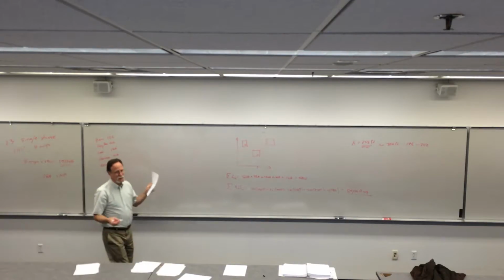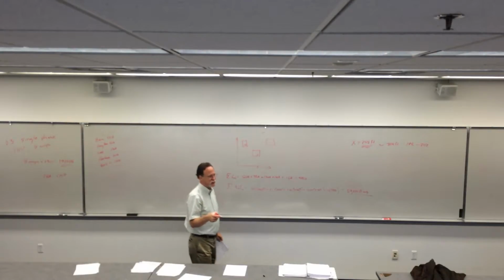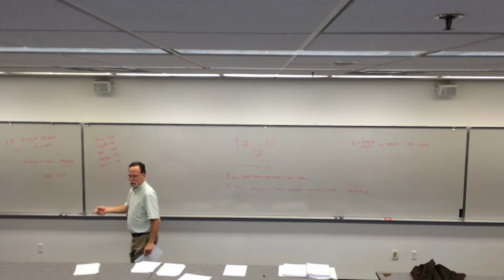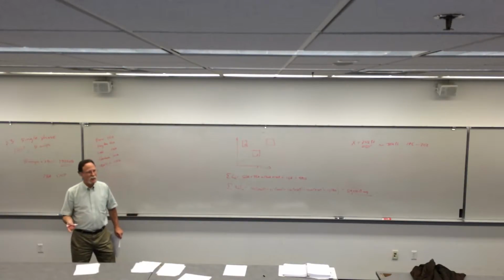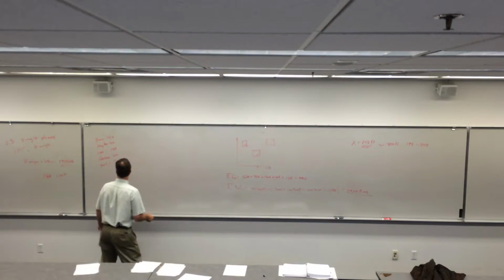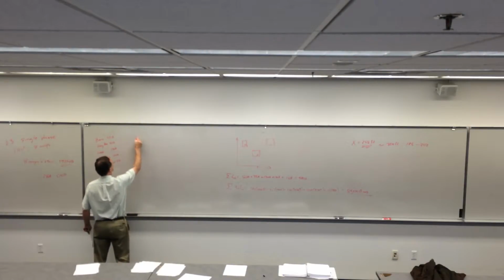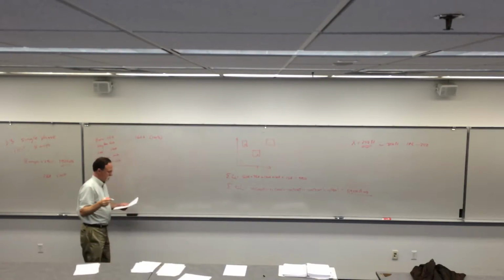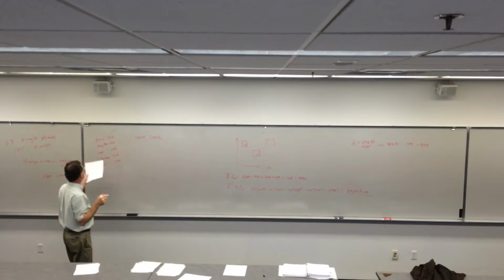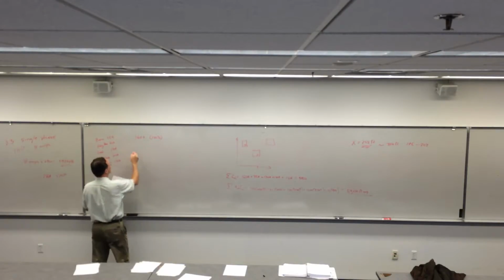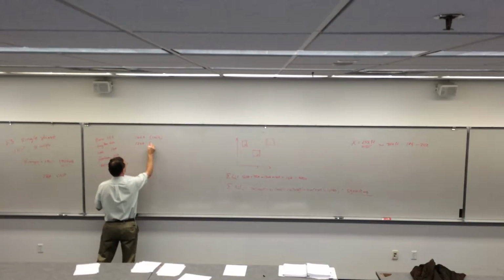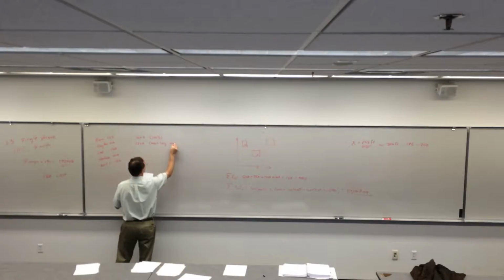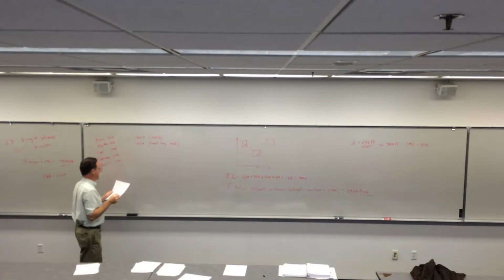How do we add that up for the main service center? It had instructions in the chapter. 100% of this, 100% of that, 75, so what was the first instruction? Residence is 100%. So 160 amps, 100%. Okay, what's next? The next largest is 100%, so 120 amps next. The largest is also 100%. Okay, we're good to go here. How about after that?